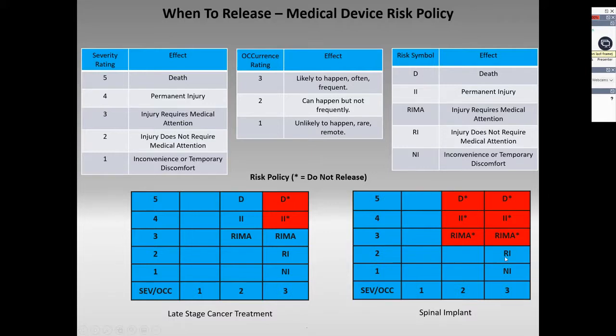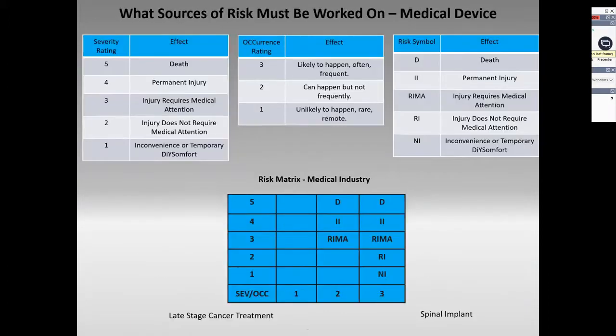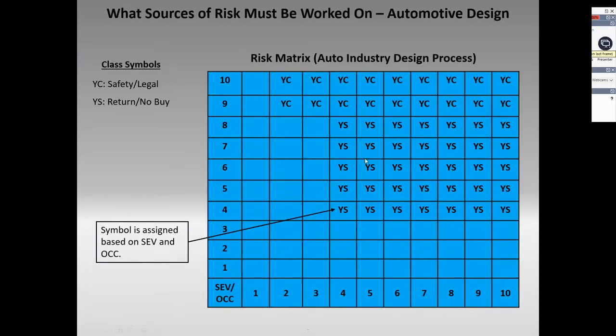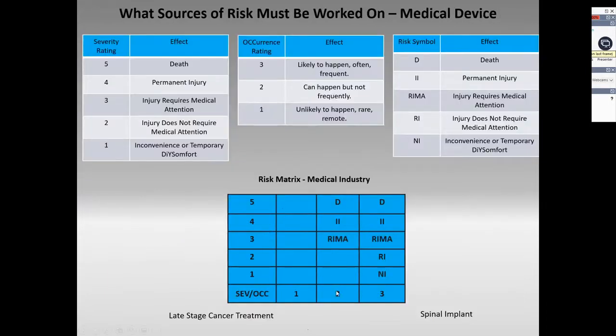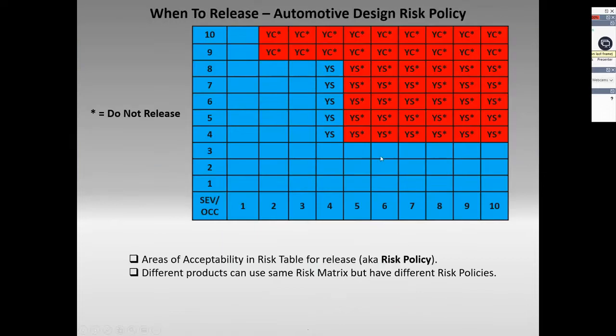I do expect to be sore, some discomfort - so these are acceptable. Whereas over here, when it comes to stage four, late stage cancer treatments, the bottom line is these can be acceptable risks because here I'm going to be saving patients' lives. So depending on the type of software you're developing, you're going to need two things: a risk matrix identifying what combinations of severity and occurrence are acceptable, and a risk policy that tells you at what level of risk you release the software for use.